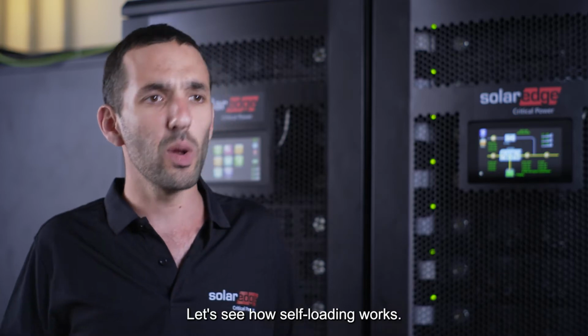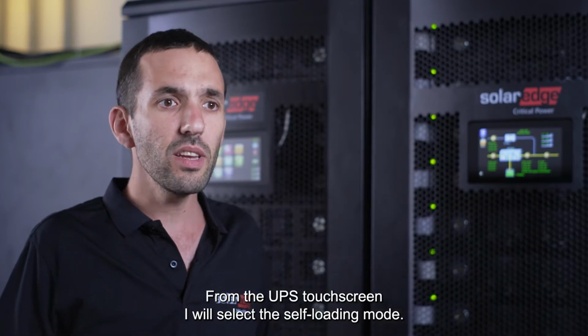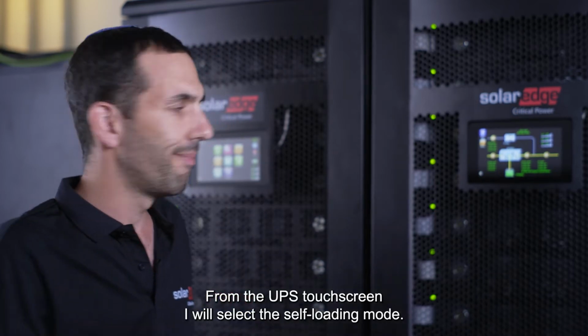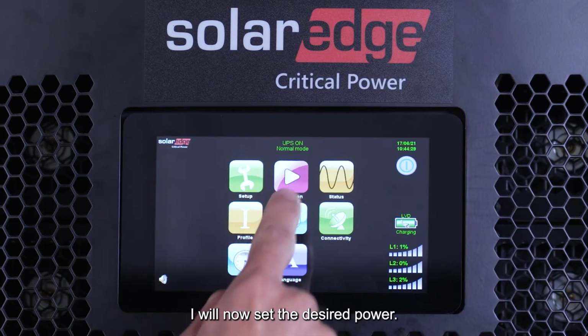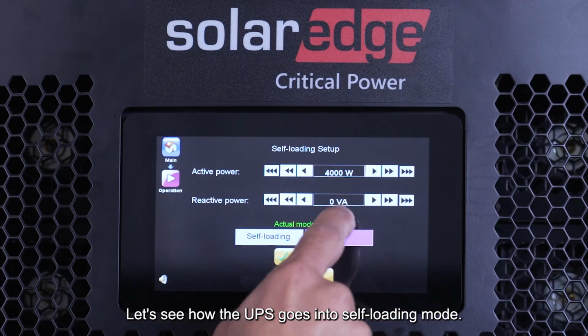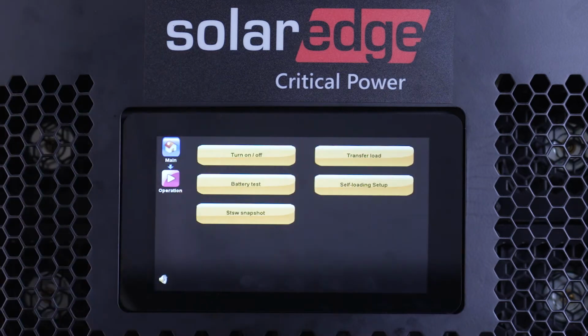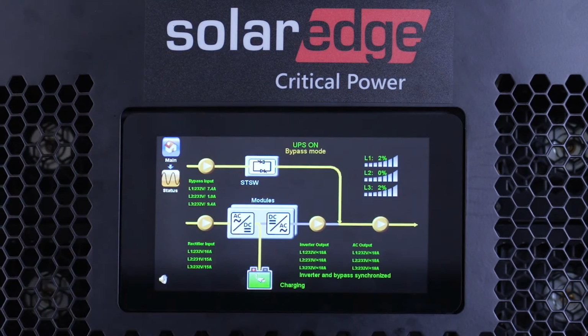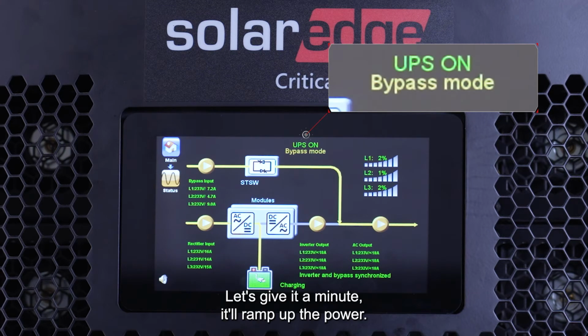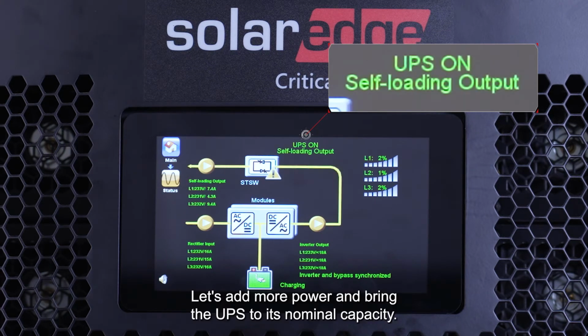Let's see how self-loading works. From the UPS touchscreen, I will select self-loading mode. I will now set the desired power. Let's see how the UPS goes into self-loading mode. Let's give it a minute. I'll ramp up the power. Let's add more power and bring the UPS to its nominal capacity.